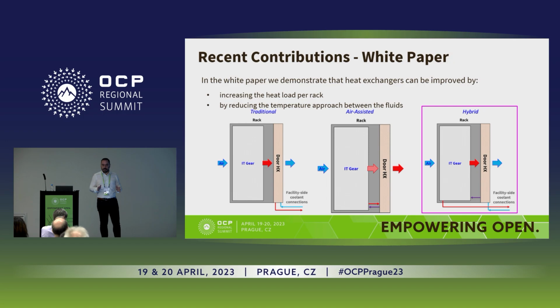It's not a problem. If you are increasing the power, this is more difficult because you have other problems, because if you are not using fans in the rear door, maybe you have problems in the IT gear because they bypass the air into the IT gear.